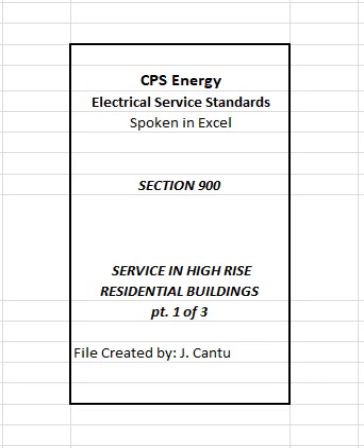The primary 3-phase pad mount switchgear will supply single-phase transformer rooms located on every third floor for tenant loads, and the 3-phase pad mount transformer will supply customer-owned service equipment at a CPS Energy approved location for house loads. Note 1. House loads shall be metered separately, and such metering equipment may be located at the transformer secondary or at customer's service equipment location. Note 2. CPS Energy will not offer a primary voltage distribution system unless a minimum of 6 transformer rooms are required, and each transformer room shall serve 3 floors with a combined load not to exceed 250 kVA.